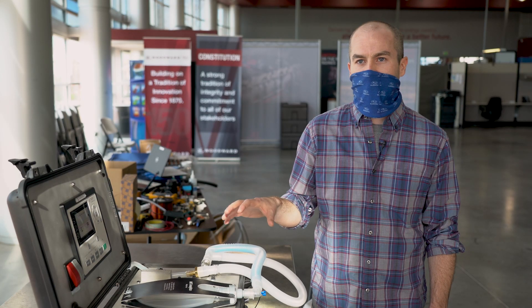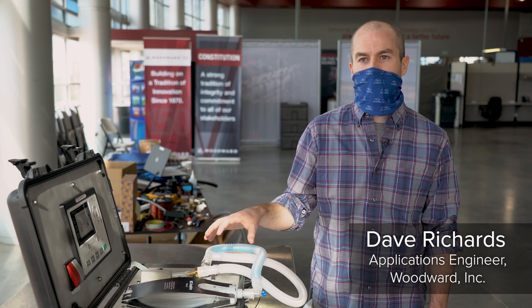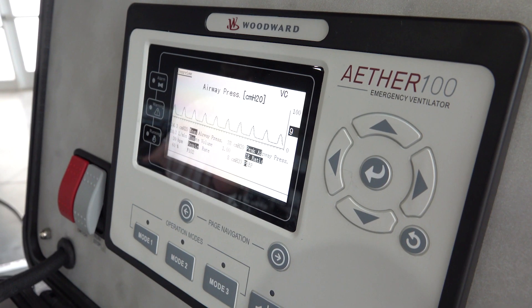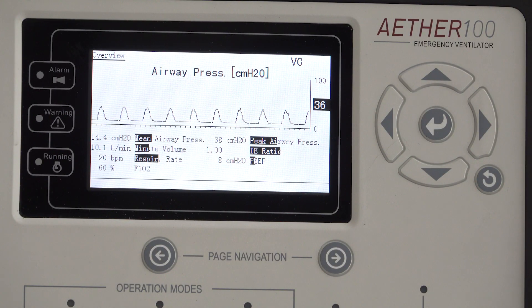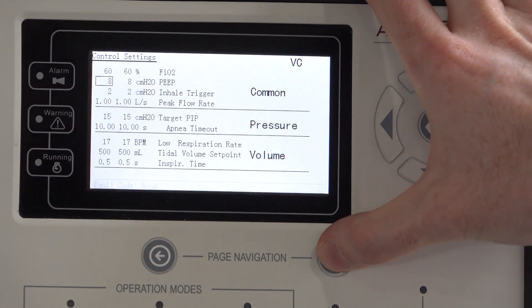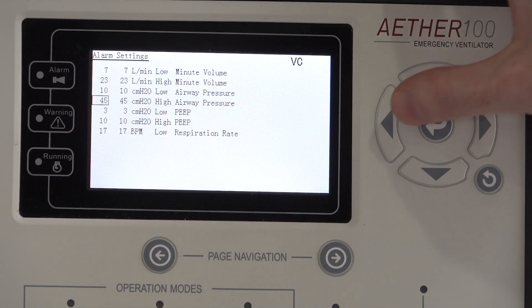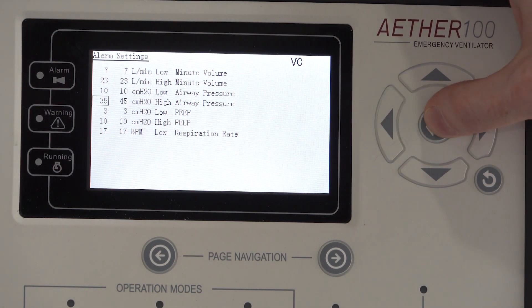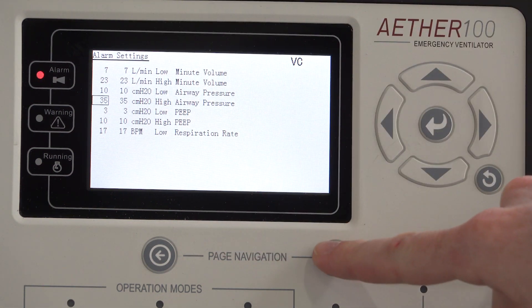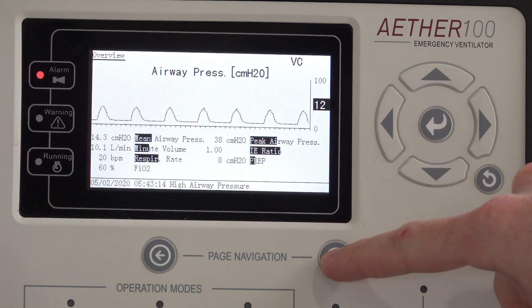The brains of the Aether 100 are a ruggedized engine controller developed by Woodward for industrial applications. Woodward has a sophisticated set of software tools developed to control airflow into engines, gas turbines, and even aircraft engines. We can develop control strategies using these powerful tools, then download the executable code to the Aether controller. The human machine interface is a ruggedized product that Woodward developed to control electronic generators, but has the functionality we need for setting patient parameters and providing feedback to the medical team.